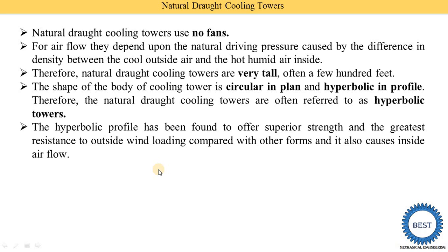There are various types of curves, but we use the hyperbolic profile for cooling towers because it gives superior strength and the greatest resistance to outside wind. When high-velocity winds occur, these hyperbolic shapes are able to resist wind load and also assist inside air flow. These hyperbolic profiles help to create natural circulation of air flow.